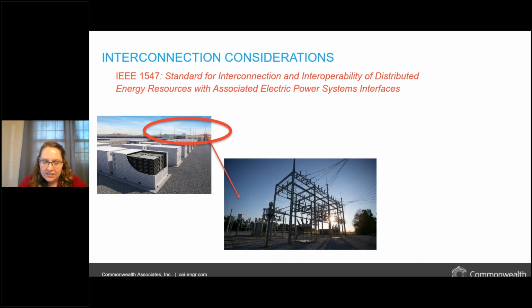So IEEE 1547 is a standard that does not describe how to operate battery systems. It does not educate us on exactly how to design those systems. But what it does is specify functional requirements, the capabilities that DER systems, like batteries in a community connection, are required to have if they're going to interconnect to the distribution grid. Topics include reactive power and active power, voltage ride-through requirements, voltage trip requirements, frequency.